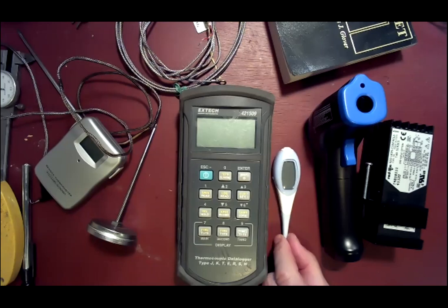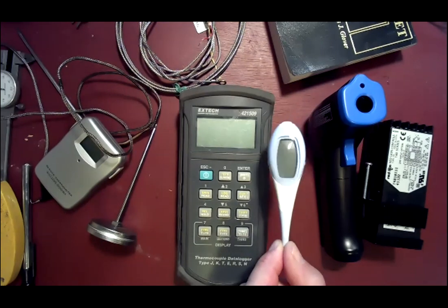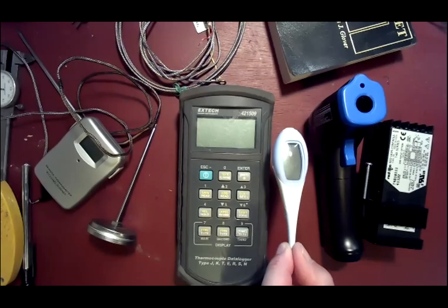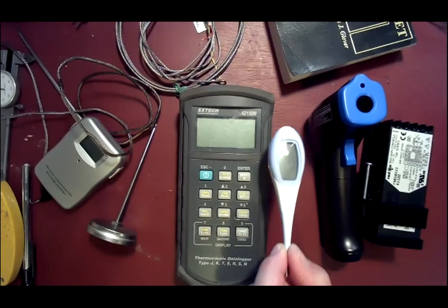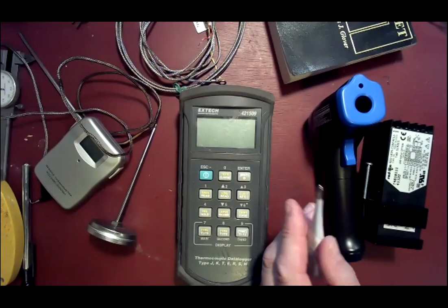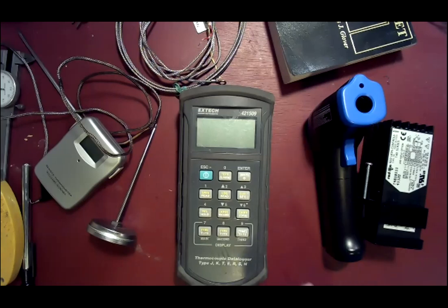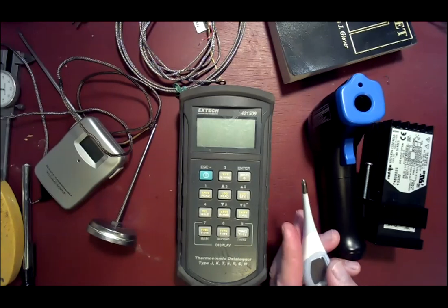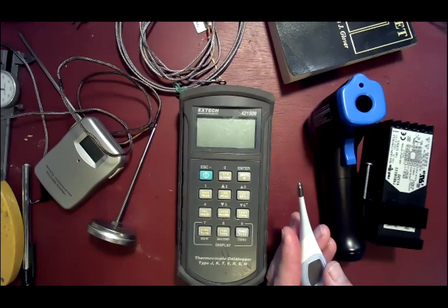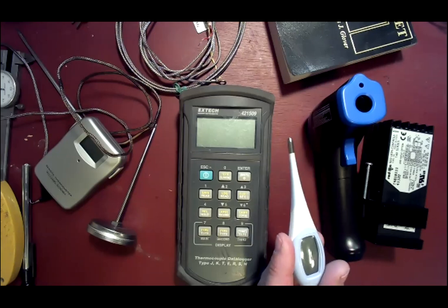So that is your classic measurement system. Now, the advantage of this system is it's automatic and it looks at temperature stability as it rises. It's relatively accurate. It uses a thermistor, not a thermocouple. We're going to learn more about thermocouples in sensors class, but thermocouples are a little bit less accurate. They're probably an accuracy of 2 degrees Fahrenheit, whereas thermistors are usually an accuracy of 0.5 degree Fahrenheit.